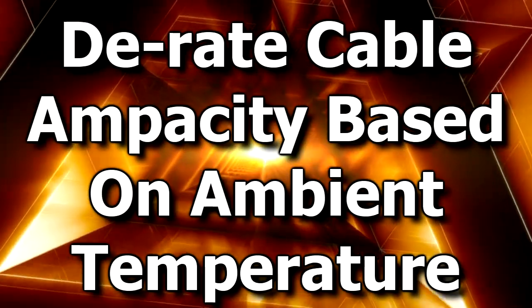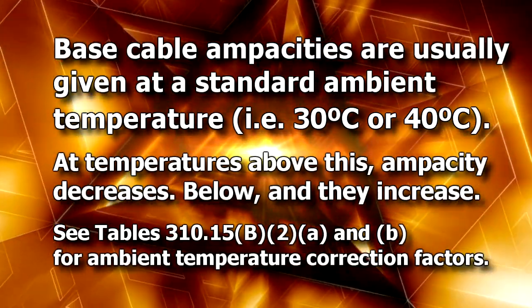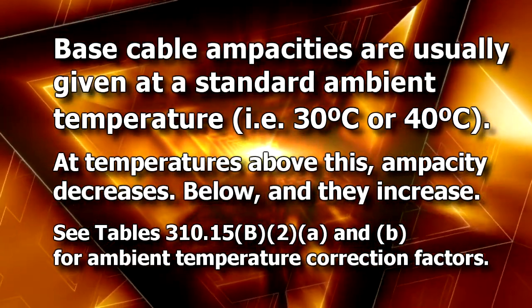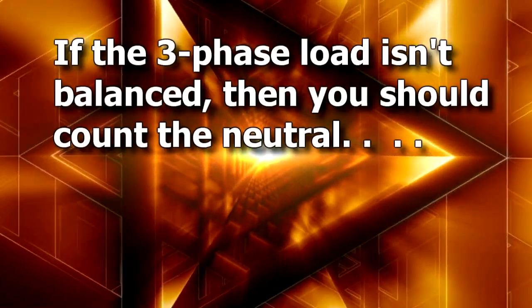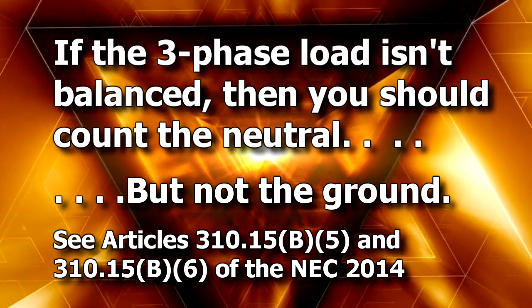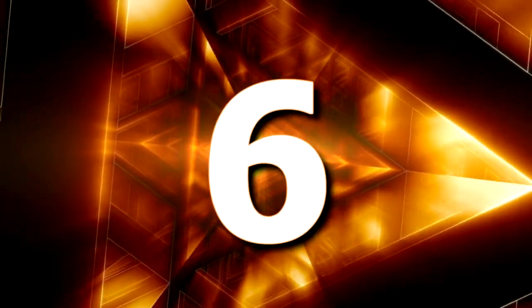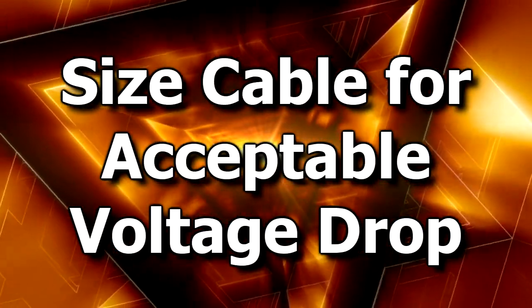Tip number four: de-rate cable ampacity based on ambient temperature. Tip number five: de-rate ampacity for number of loaded cables. Tip number six: size cable for acceptable voltage drop.